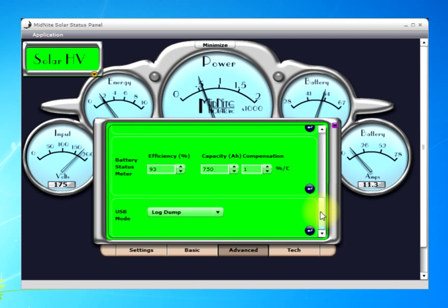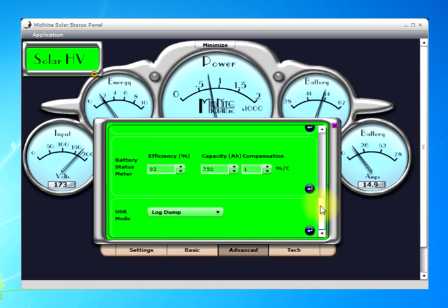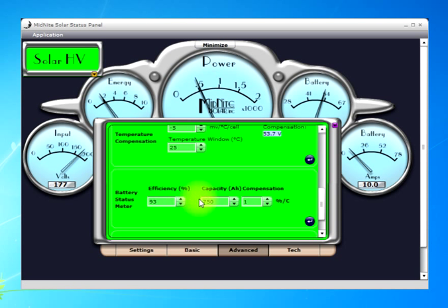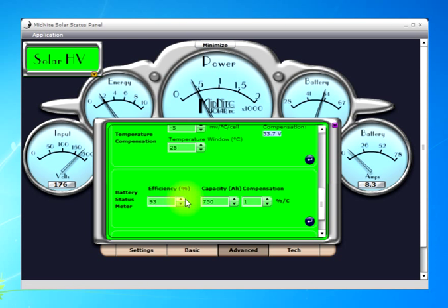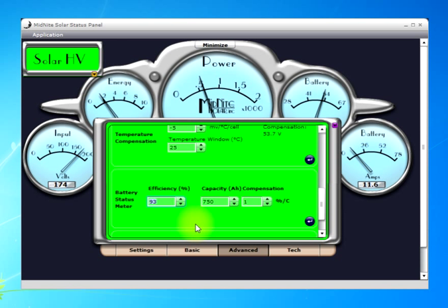The next category down is battery efficiency, amp-hour capacity, and compensation percentage. These values — including the 25 degrees C reference — are all available from your battery manufacturer. Check their spec sheets, look on the internet, or give them a call. Battery efficiency is the efficiency of the battery. Typically a battery state of charge meter will settle at 94% by default. Some batteries will be higher — if you've got an AGM or sealed battery, or if the battery is new, it might be higher than that.